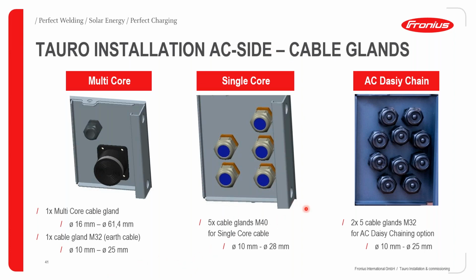If you, however, choose to go for the single core Tauro, please note with the single core Tauro, we have 5 glands, and each gland can take diameters of 10 millimeters up to 28 millimeters. Then if you're going to go for the AC chain option, okay, so in this case, you're going to have your in and your out. You're going to have your earth, live, neutral. So earth, live, neutral, and then L1, L2, L3, live and neutral. But anyways, with that, you get a diameter per slot of 10 millimeters to 25 millimeters.